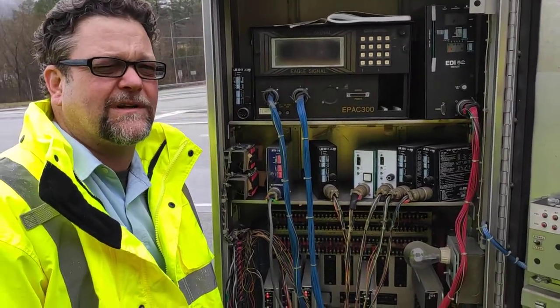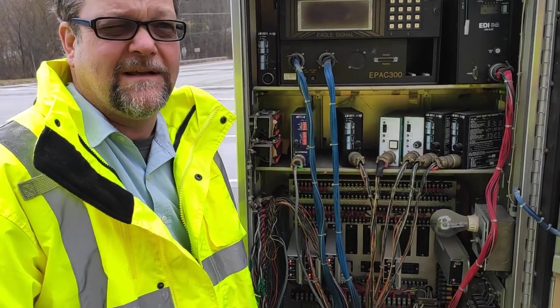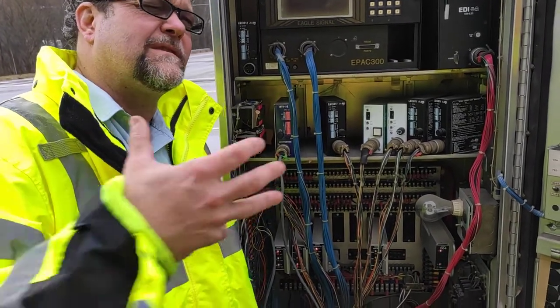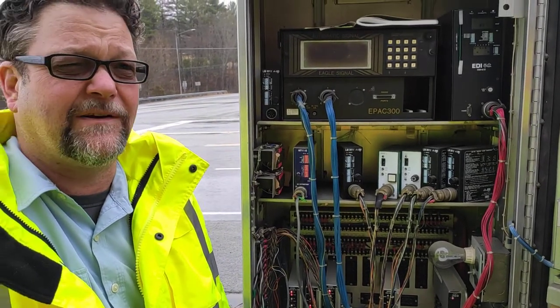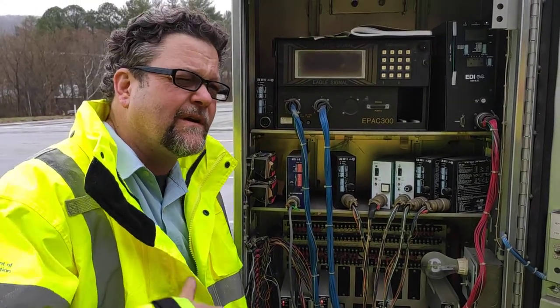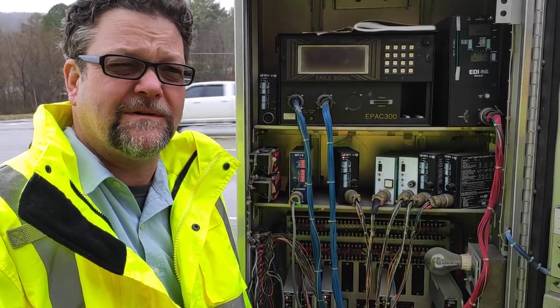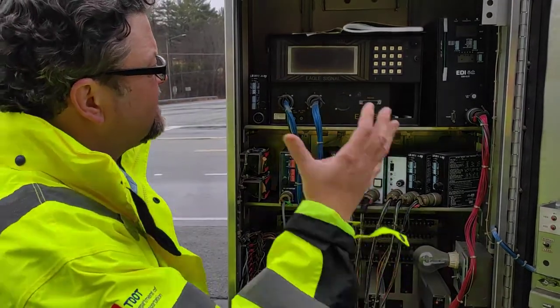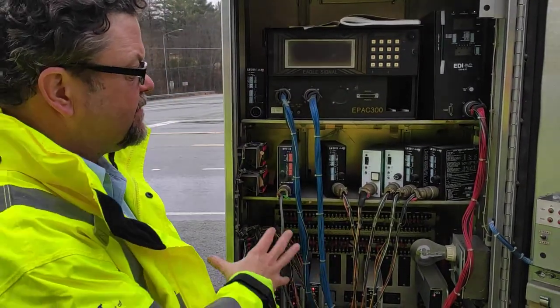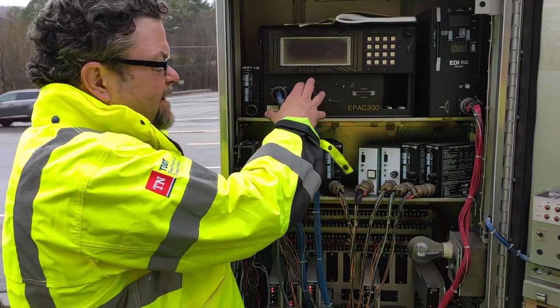This is a TS1 cabinet. There are a couple different flavors for NEMA. We're pretty much a NEMA state — most of the stuff you'll see in Tennessee is a NEMA TS1 standard. It's about a 30-year-old standard, pretty old. Now they're starting to go more modern, so the other two standards are NEMA TS2, Type 1 and Type 2. We'll talk about those, but let's familiarize you with the cabinet itself.